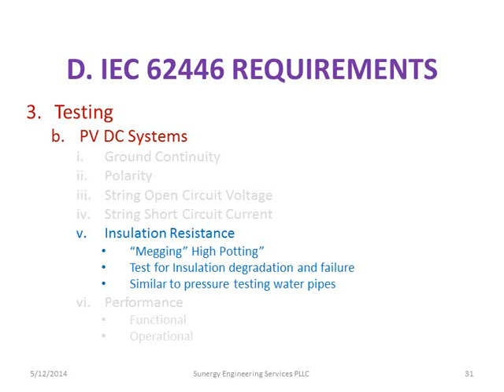And that can be done with a normal, off-the-shelf Megger. Basically, you put your negative onto the ground, and you put your positive onto the negative conductor, and then you have to choose a voltage level that you'll do the test at, and it just puts a small amount, a couple hundred milliamps, I believe, into the circuit, and then you can test the circuit like that.